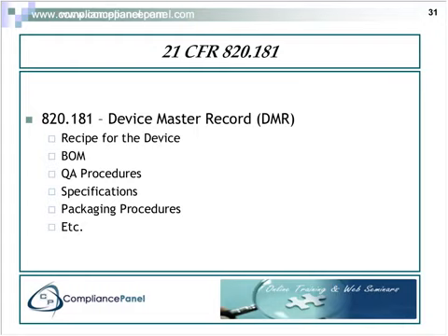It's important to understand that each time a device's revision changes, the device master record also changes. It's required that we have a sound and documented methodology for creating, maintaining, and changing the device master record. And again, this methodology should be covered by a combination or a single operational document that's maintained by your organization.